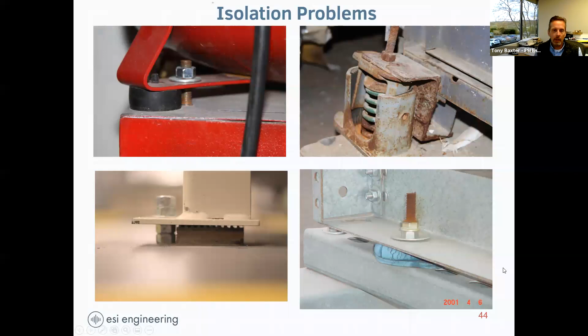This is real common. We go in and see that the springs are fully compressed. They adjusted them all the way down to lift this inertia base off of the housekeeping pad, but the springs weren't stiff enough, or there's too much load, but it's been adjusted all the way down, so it's compressed.